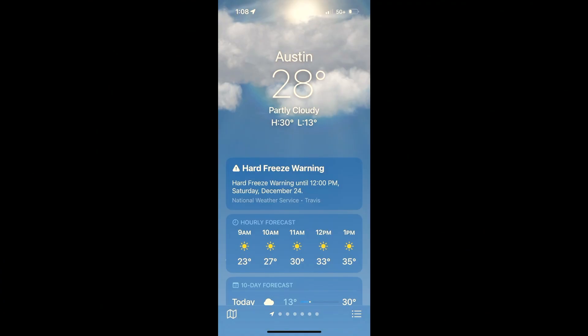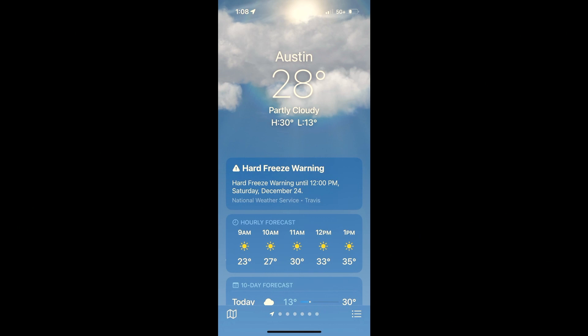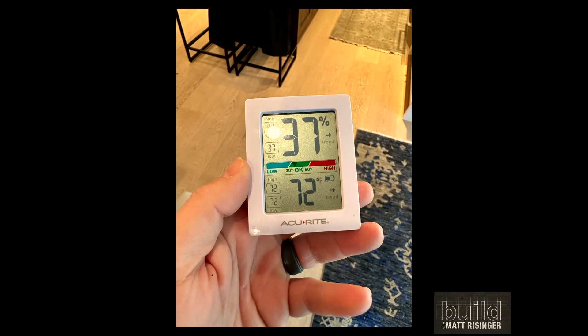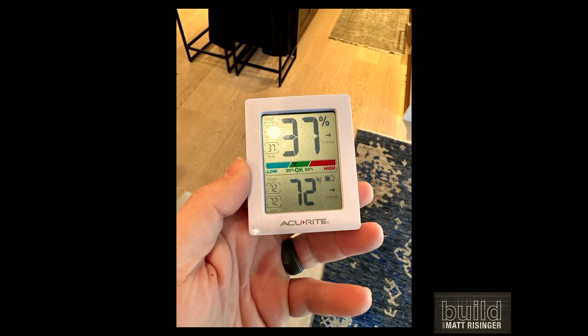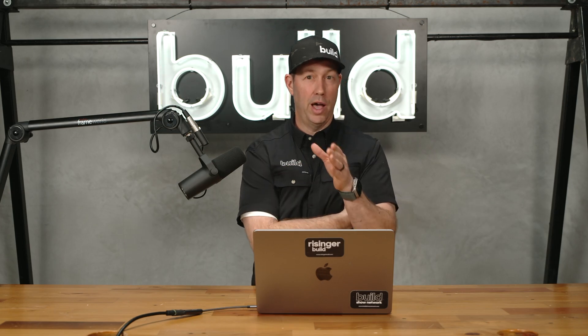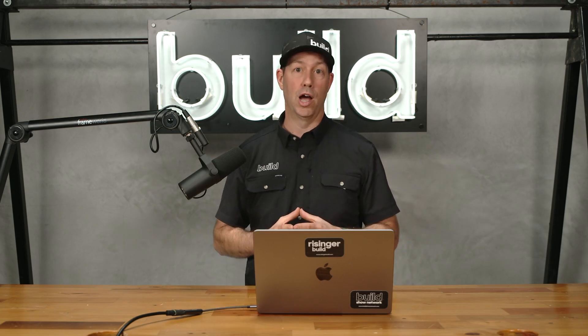Let's look at the conditions when I took this video. From my iPhone it was 1 o'clock in the afternoon. Outdoor temperature was 28 degrees — a little chilly for Austin but not cold for many in the north. Overnight lows were 13 degrees. Indoor conditions: 72 degrees at 37% relative humidity. That's a pretty low humidity setting — most dehumidifiers won't get you below 40% or 35%. So this isn't a high-humidity event; it's not that someone forgot to run the bath fans.